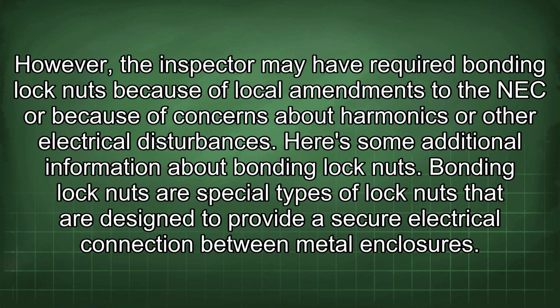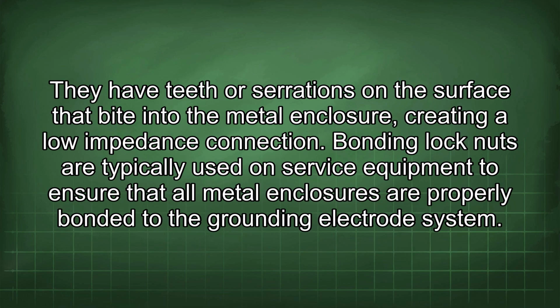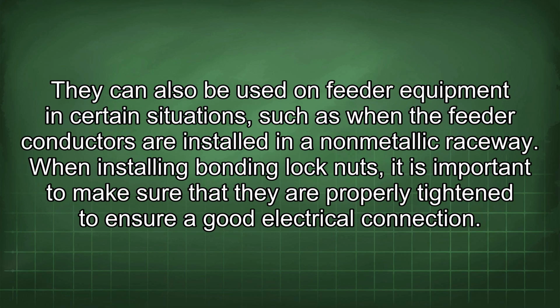Here is some additional information about bonding lock nuts. Bonding lock nuts are special types of lock nuts that are designed to provide a secure electrical connection between metal enclosures. They have teeth or serrations on the surface that bite into the metal enclosure, creating a low impedance connection. Bonding lock nuts are typically used on service equipment to ensure that all metal enclosures are properly bonded to the grounding electrode system. They can also be used on feeder equipment in certain situations, such as when the feeder conductors are installed in a non-metallic raceway.